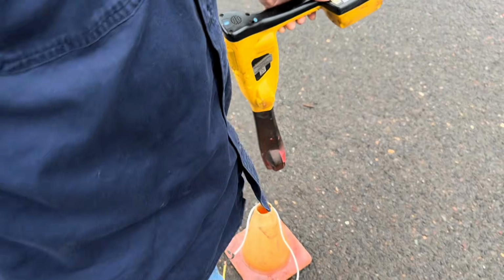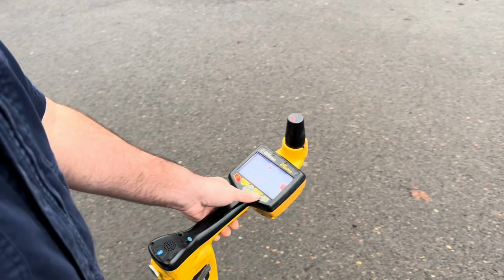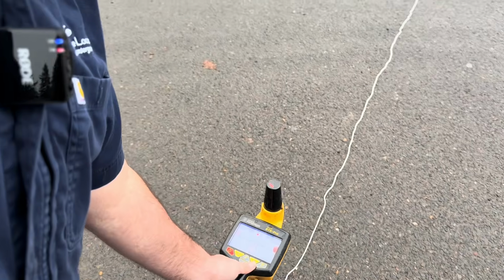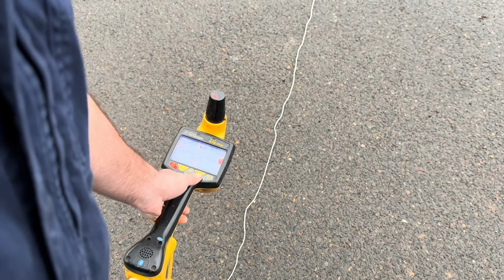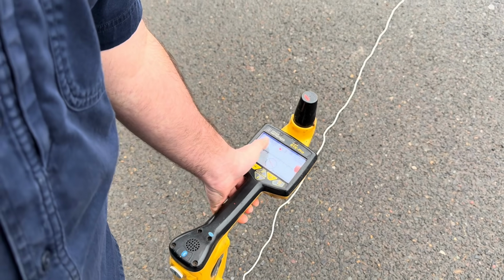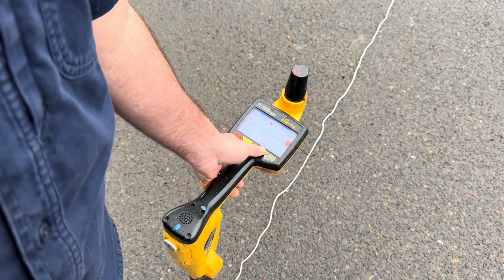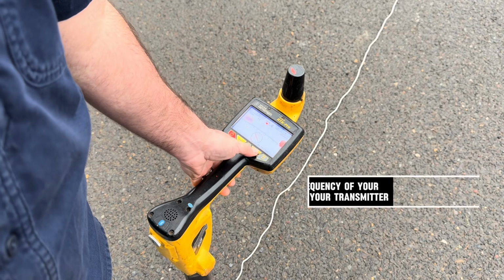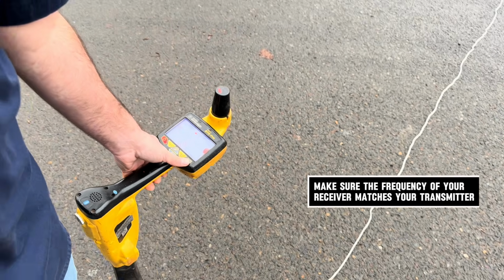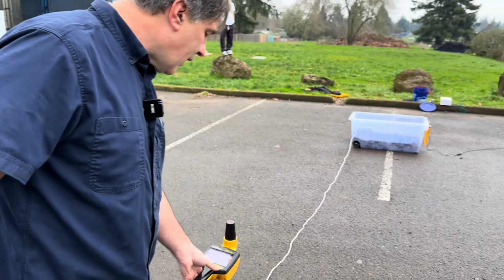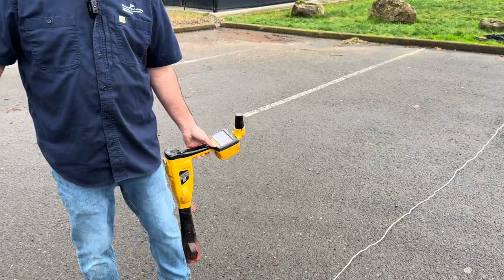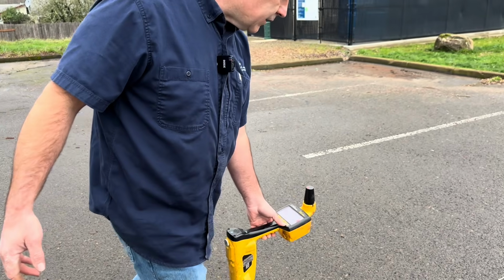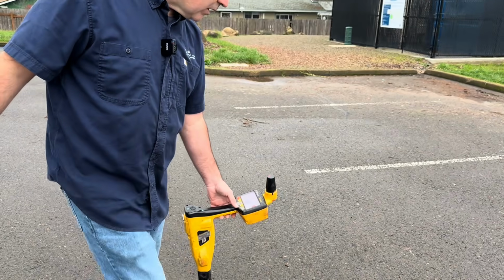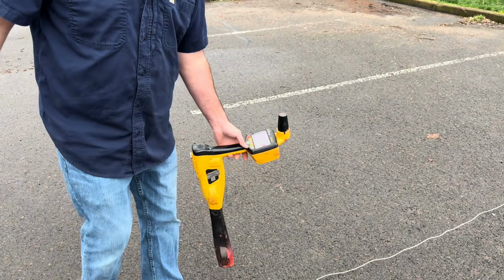And when we get over here, you kind of get a little wiggle there. My milliamps are down drastically. I've got my gain set pretty low. So now I'm at 0.30 milliamps, so I can definitely tell that there's something wrong in that location. But here you go, I'm able to locate out the utility.